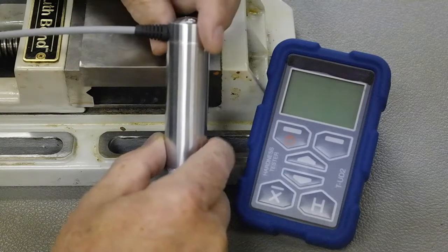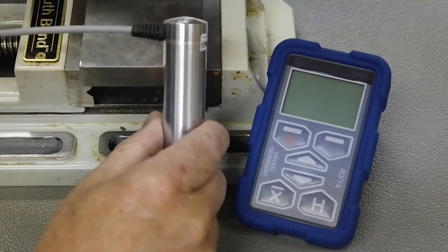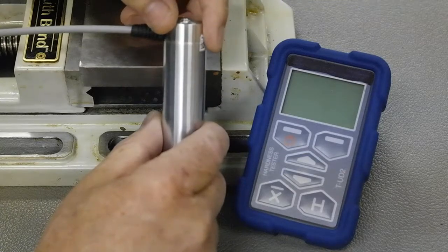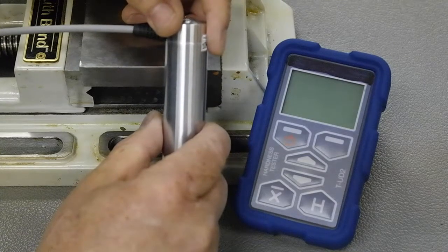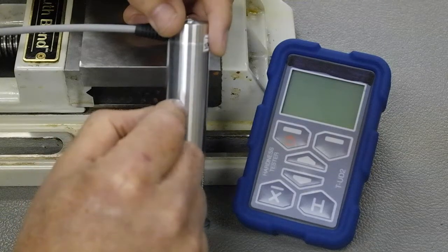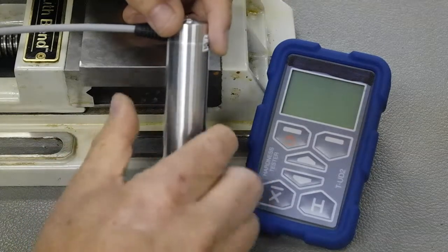Now, because it's volatile memory like that, if you unplug and plug it back in again, it's like removing a SIM card from a phone, for example, whilst it's powered on. There's a very good chance you're going to wipe the memory. In this case, you're going to wipe out the calibration settings, and you'd have to recreate them.